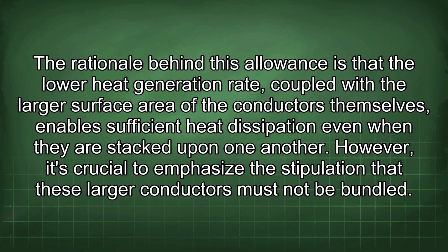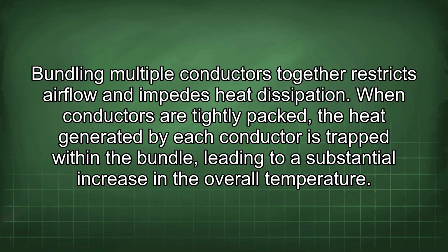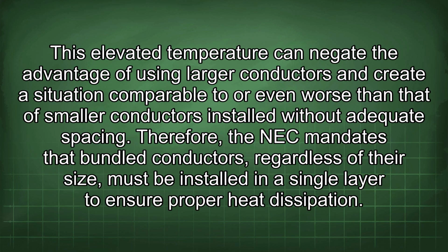However, it's crucial to emphasize the stipulation that these larger conductors must not be bundled. Bundling multiple conductors together restricts airflow and impedes heat dissipation. When conductors are tightly packed, the heat generated by each conductor is trapped within the bundle, leading to a substantial increase in the overall temperature. This elevated temperature can negate the advantage of using larger conductors and create a situation comparable to or even worse than that of smaller conductors installed without adequate spacing.